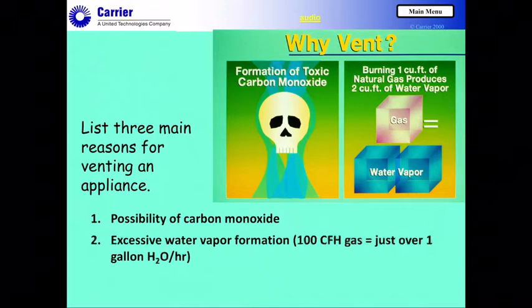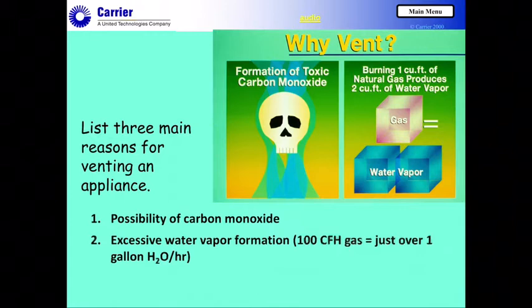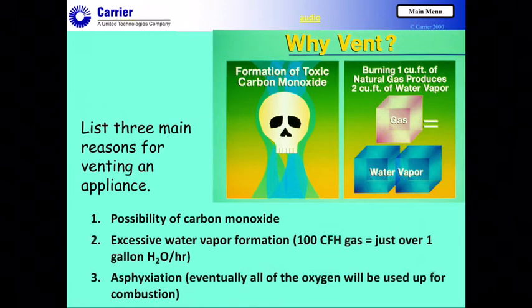When you're burning roughly 100 cubic feet of gas per hour — that's about 100,000 BTUs — just running a furnace for an hour, you can produce just over a gallon of water. That's a substantial amount of water we have to be concerned with.